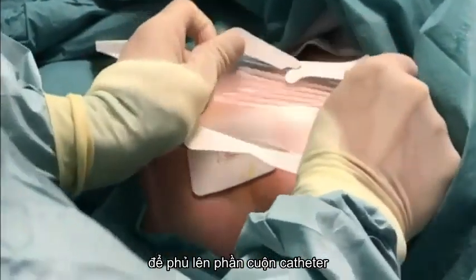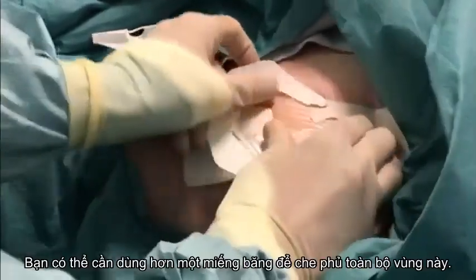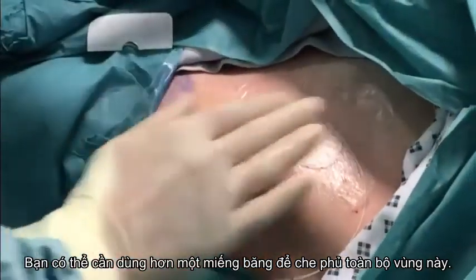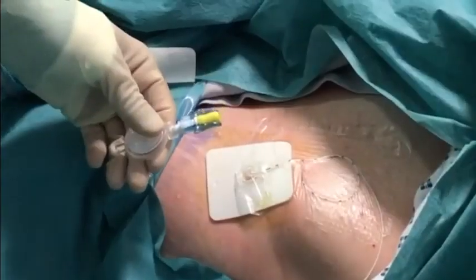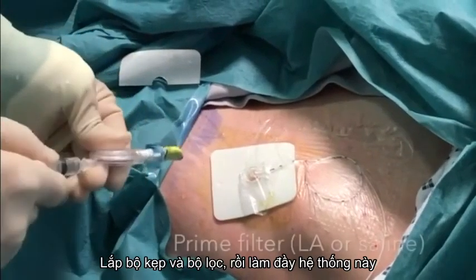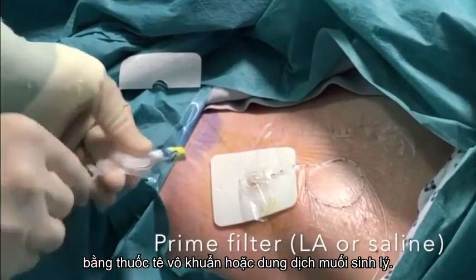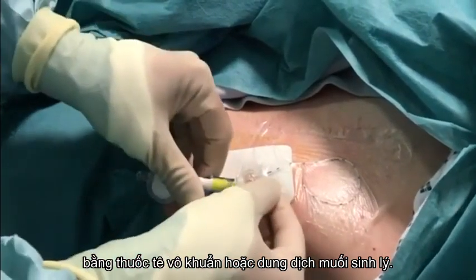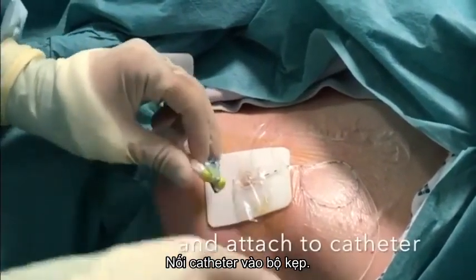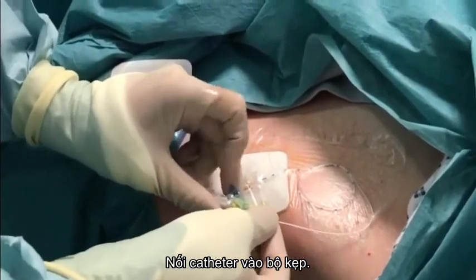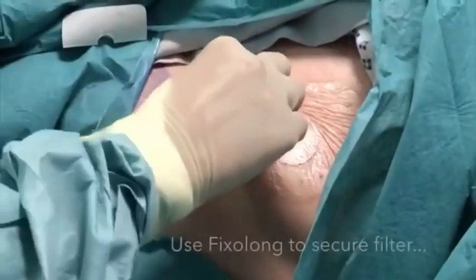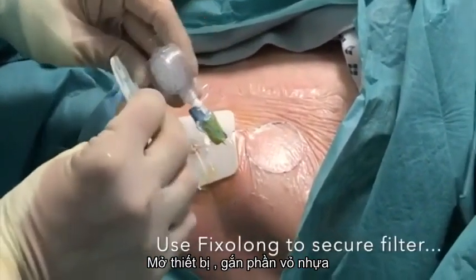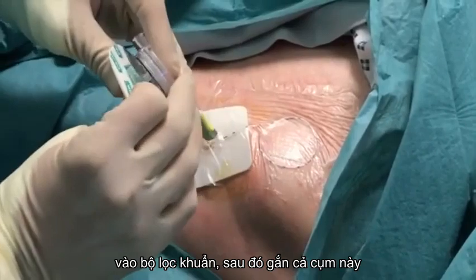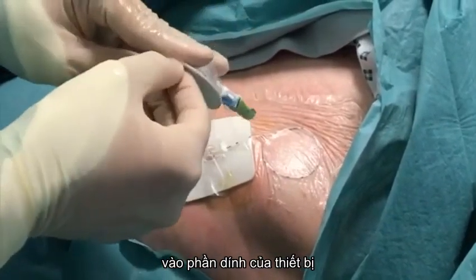Take a clear adhesive dressing and use this to cover the catheter coil and the exit site of the catheter from the skin. You may need more than one dressing to cover the whole area. Assemble the clamp and filter and prime this with sterile local anesthetic or saline. Connect the catheter into the clamp. Open the Fixolong device and clip the shell part onto the bacterial filter. Then click this into the adhesive part of the Fixolong device.